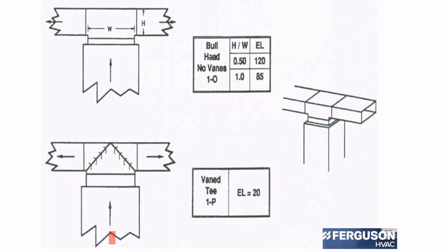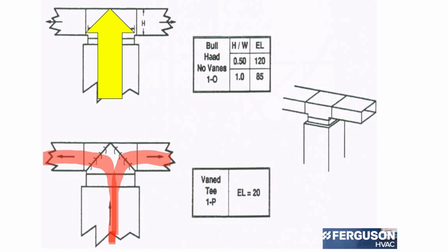As we said before, air is stupid. And when you have a bullhead with no vanes in it like this and a lot of right angles, air is going to come out of the furnace or air handler and hit the top of this ductwork and will rebound back into the furnace and cause turbulence and recirculation. By simply putting turning vanes into this type of fitting, you're going to reduce the equivalent length from 120 feet down to 20 feet.